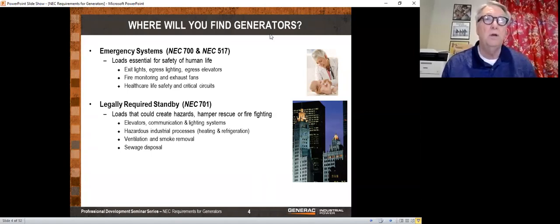Both emergency and legally required are required by your local jurisdiction. You don't get a choice for whether you have a standby generator, it's required. So if you need an elevator in order to get out of the building, you have to have a standby generator. You don't get a choice. A legally required generator is a little less critical than emergency.